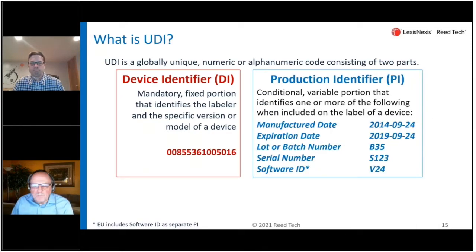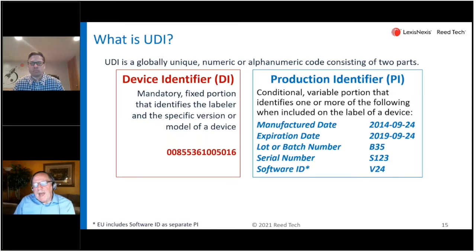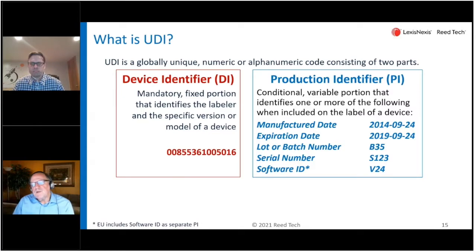The second portion that follows is referred to as a production identifier. In the event there are various production controls placed on the label, these would be added to the UDI to make up the full UDI. If they don't appear on the label, then none of these production identifiers would be there, and you remain just with the device identifier.